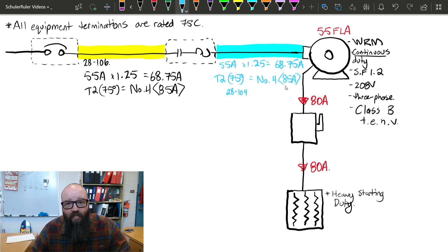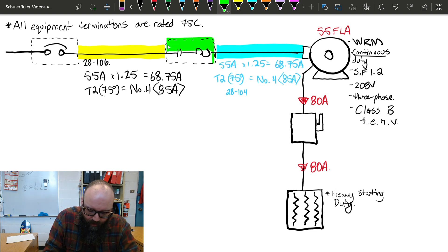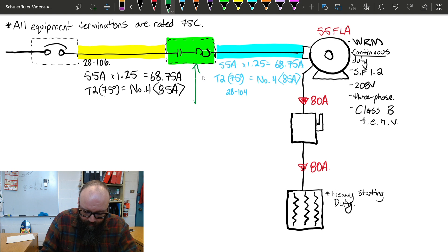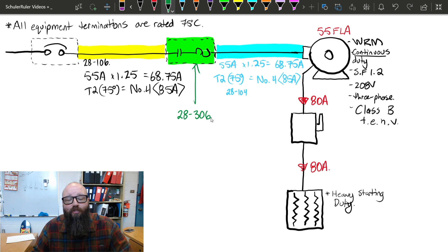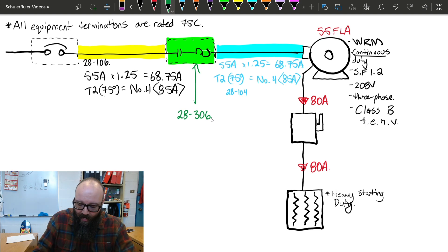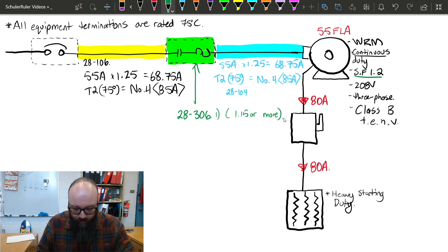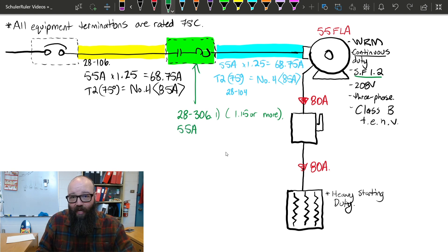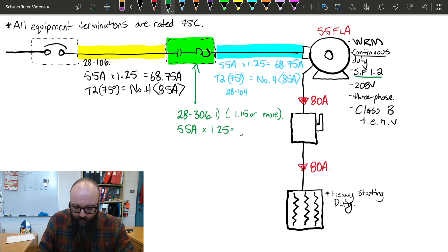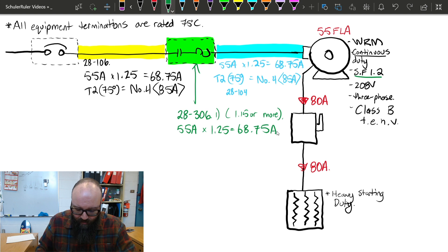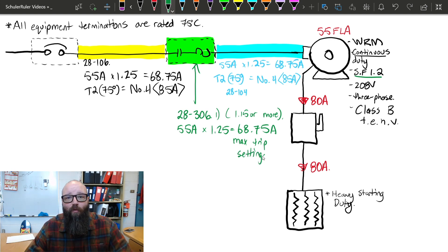Now for overloads, dealt with in 28306, we have to look at the service factor to determine our multiplying factor for the maximum trip setting. We have a service factor of 1.2, and 28306 subrule 1 says if we're dealing with 1.15 or more, we use 1.25 as our multiplier. So starting with our 55-amp FLA and multiplying by 1.25, this gives a maximum trip setting of 68.75 amps. If this were an adjustable type of overload, we could dial it up to a maximum of 68.75 amps.